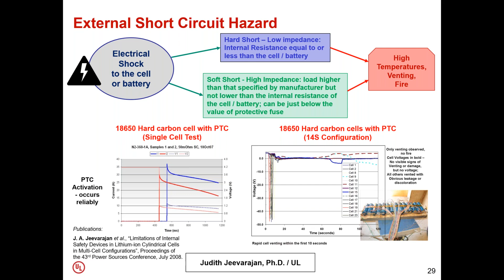And what we found is that the internal protective device in an 18650 cell, which is a PTC, has a voltage limitation. At a single cell level, it works 100% of the time, and it's resettable. But when we put cells in series or in parallel connections, we found that the PTC ignites. And this is because it has a threshold voltage limit. When a PTC activates in a high voltage environment, it actually ignites. And when you have a hard short which is creating heat and the PTC is igniting, you can have a catastrophic thermal runaway. So again, we need to understand the limitations of the protective devices, test in the relevant configuration and environment, and make sure that the protective devices are working.